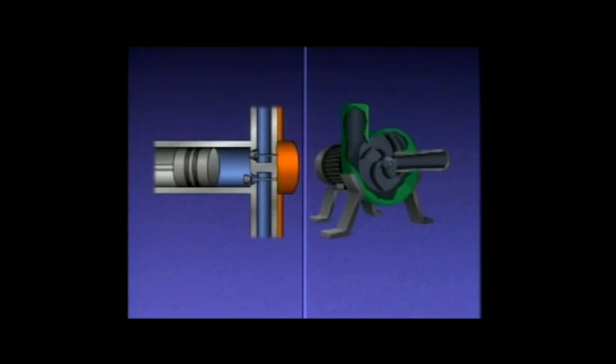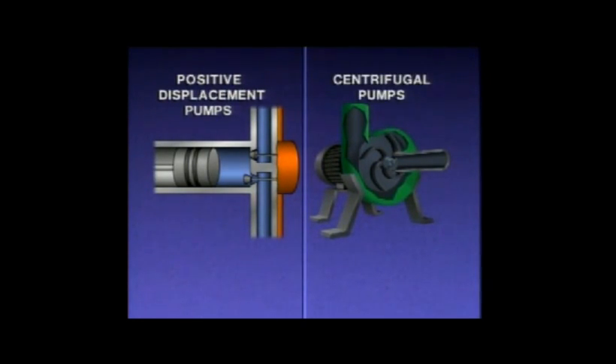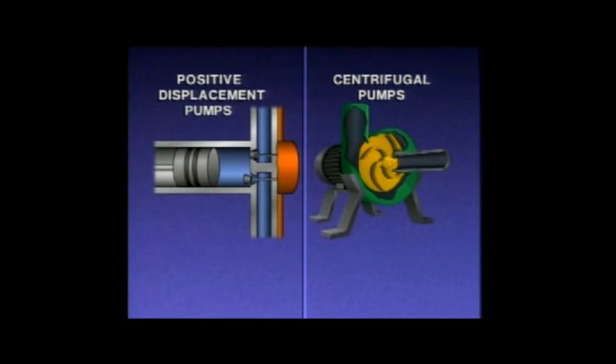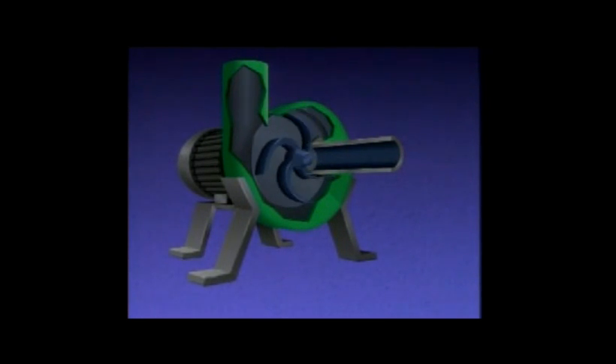Basically, pumps can be grouped into two general categories: positive displacement pumps and centrifugal pumps. A positive displacement pump uses a piston or some other device to push, or positively displace, controlled amounts of liquid through the pump. A centrifugal pump, on the other hand, uses an impeller which creates a centrifugal force to move the liquid — a force that develops when something moves or spins in a circular motion, pushing the liquid away from the center of rotation and out of the pump.